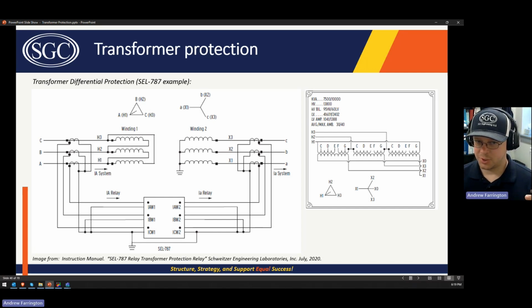But those currents don't relate to each other because they're shifted by 120 degrees. So you need to account for that in the compensation settings of the relay. And we'll get into more details on that, but I just want to bring that up because sometimes you need more details about the system than just the elementary diagram, right? That would be extremely confusing if you didn't understand that and know that going into setting the relay, that you need to shift everything by 120 degrees. So just be aware of that.